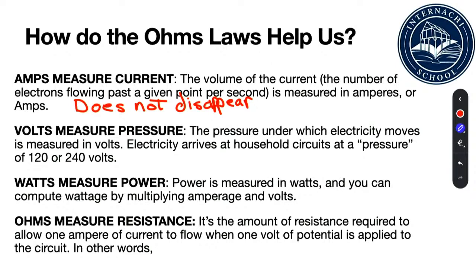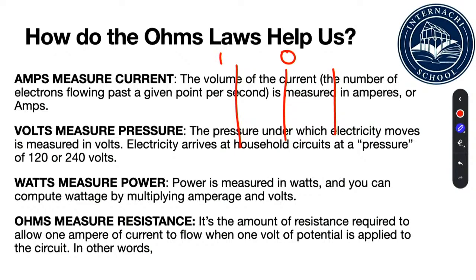Now, they will cancel out, mind you. If I have a 240 volt circuit with 3 wires coming in—1, 2, 3—let's say this is my neutral, and this is my first energized conductor at 120 volts, and this other one is also 120 volts. If I have 5 amps flowing on this one and 5 amps flowing on that one, since these 2 wires are always 180 degrees out of sync with each other, when this one is a positive 5, this one's going to be a negative 5.